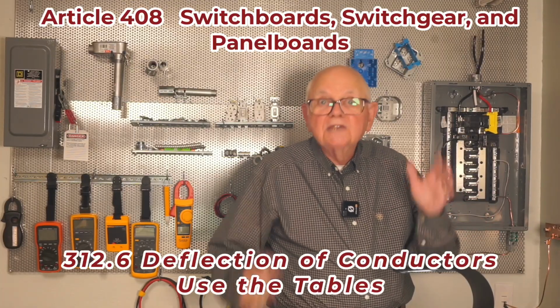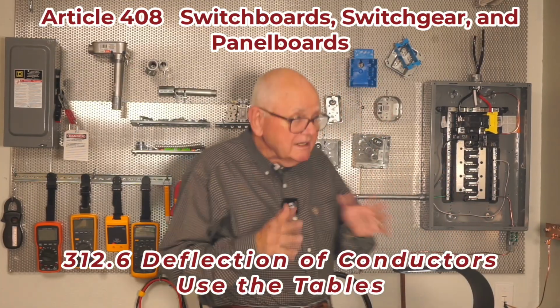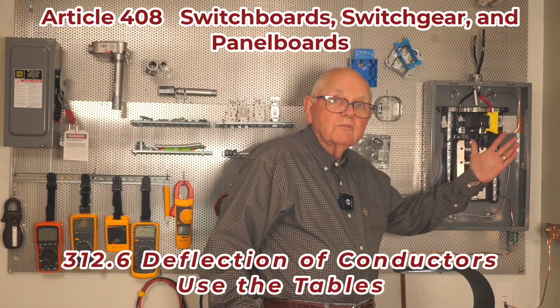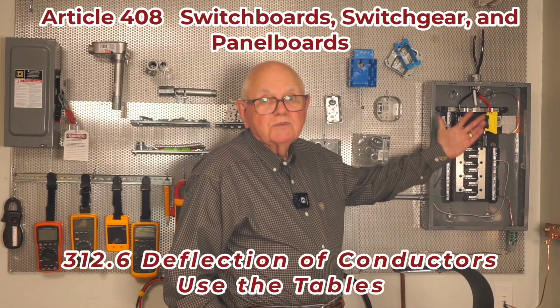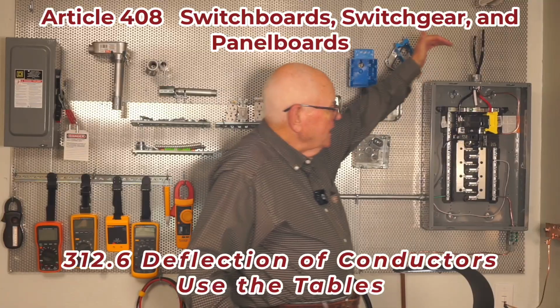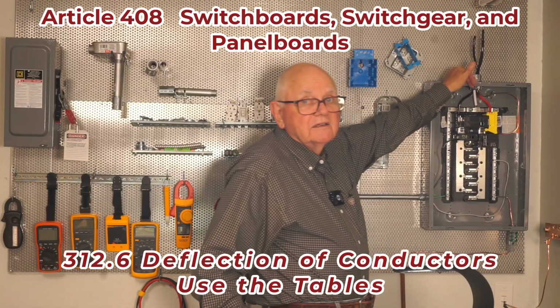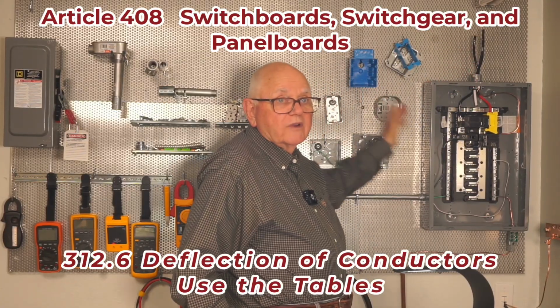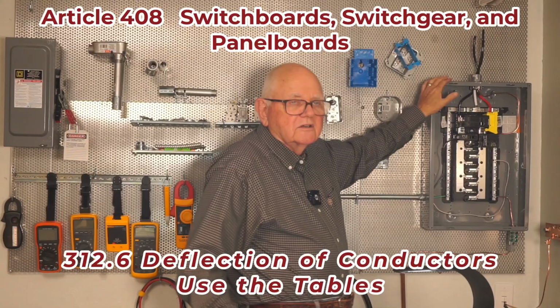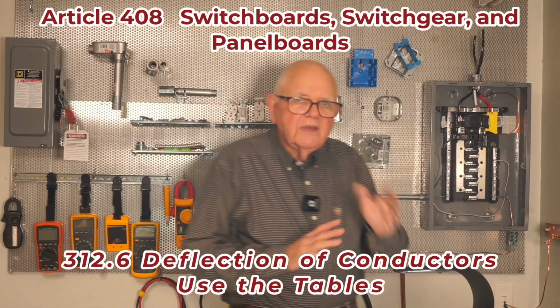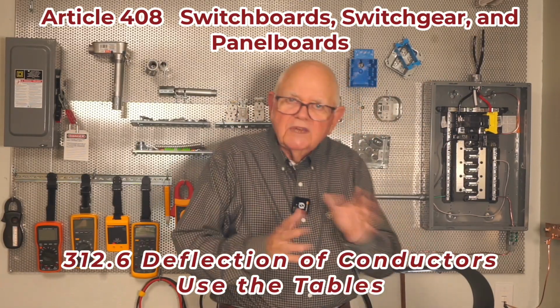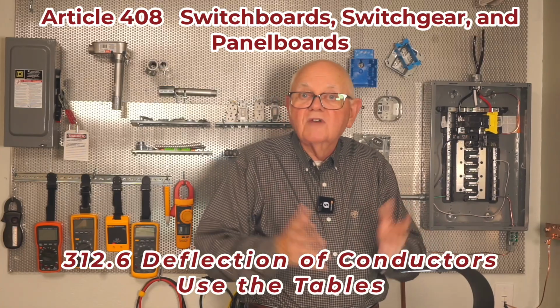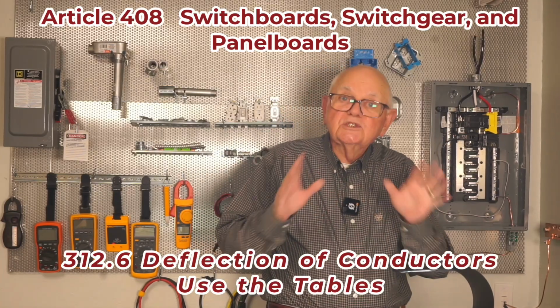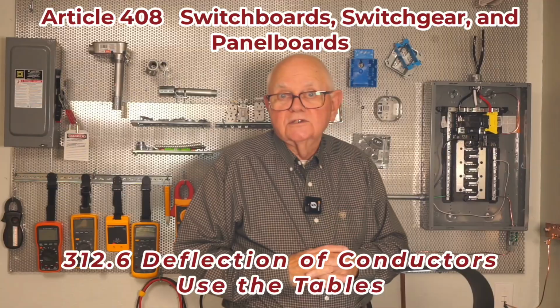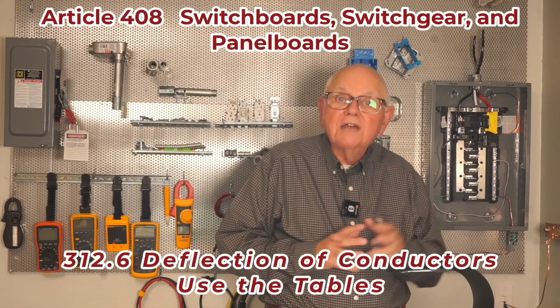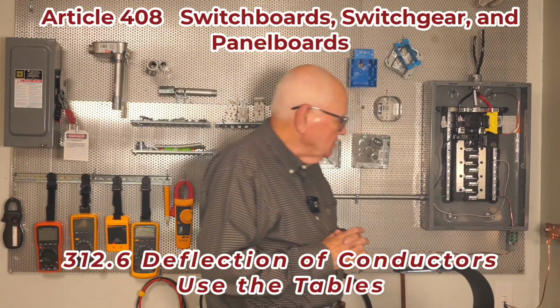And it has two tables in it that tell us, based on the size of the conductors we're bringing in, their number of conductors per terminal, and whether I'm bringing them in straight into where I'm going to terminate them, or whether I'm bringing in from the side and have to deflect my conductors and so forth. Based on all of that, I look in my table based on the size of those conductors and read across to the right, and it tells me how much space I must have to deflect those conductors in. So that's 312.6. Take a look at those tables as you need to.